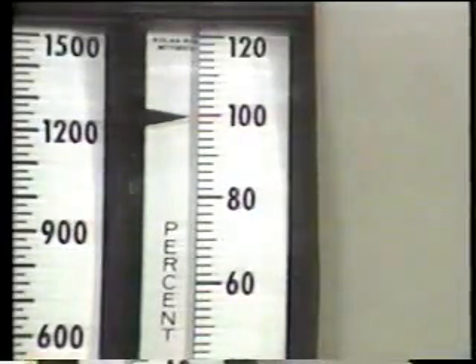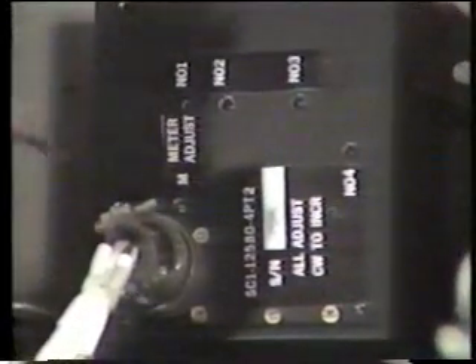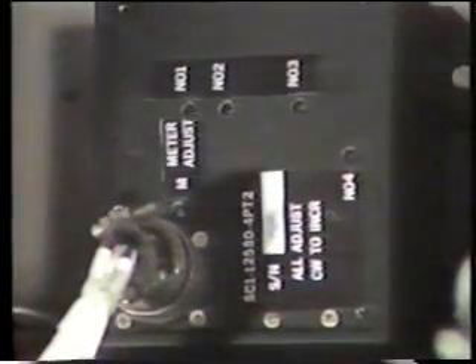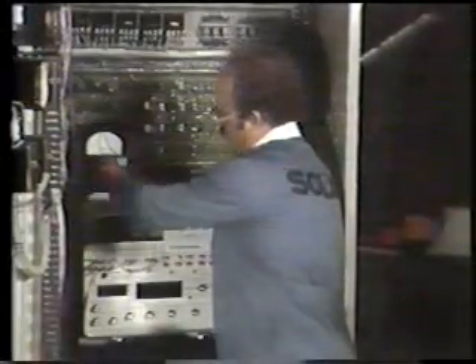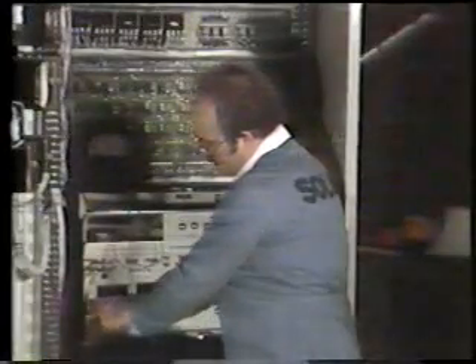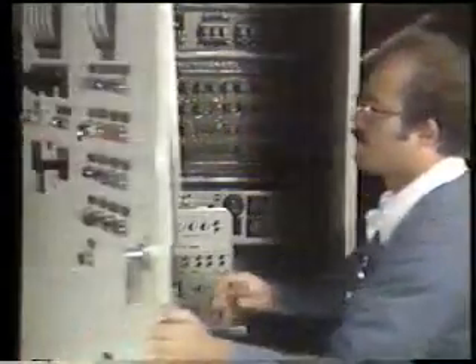If the speed control meter does not indicate 100% speed, readjust the master potentiometer. Then go back and recalibrate all set points. If calibration does not repeat after 2 attempts, replace the speed control box. If the meter indication is correct, secure power to the test equipment and to the control console. Then remove the leads from the test equipment.